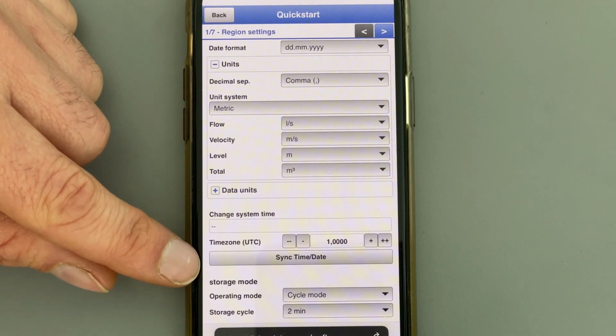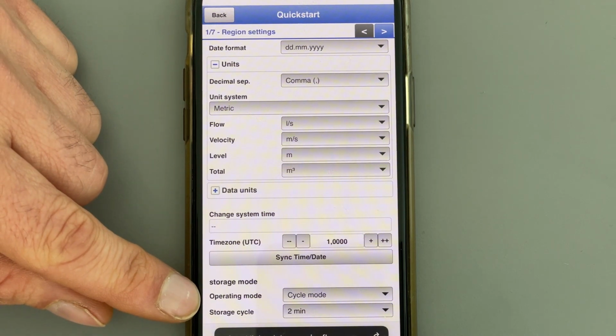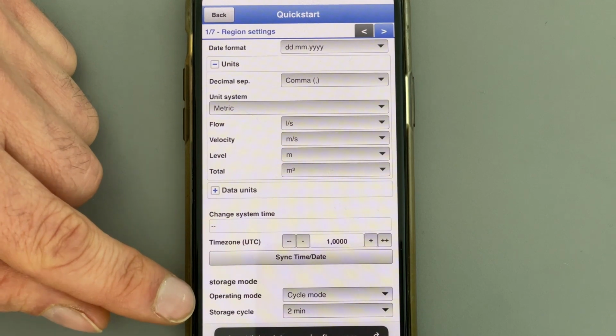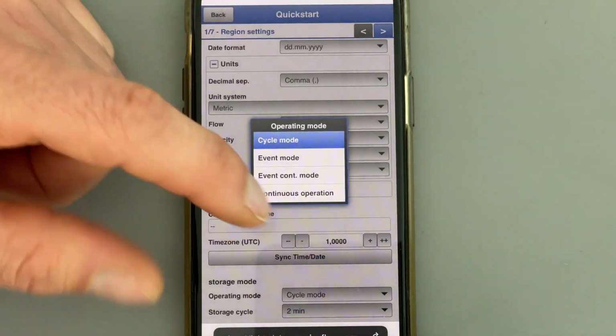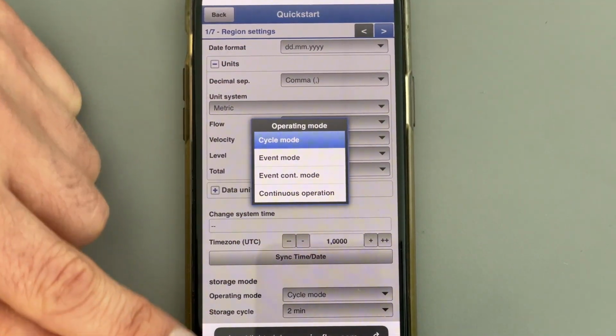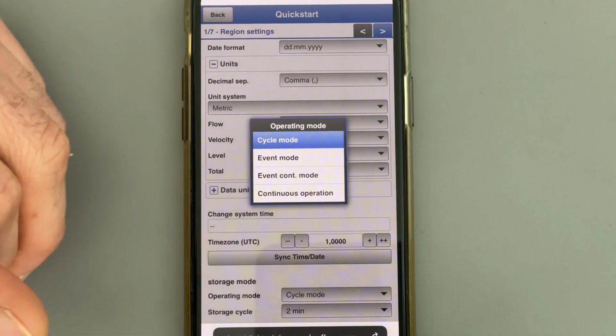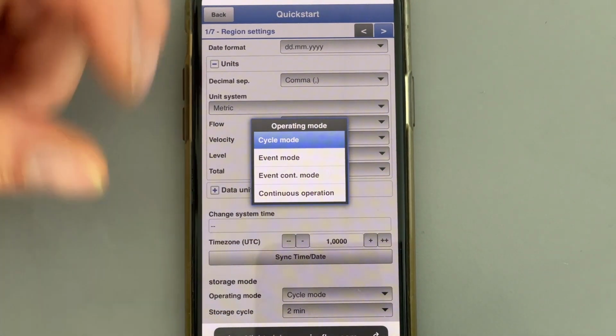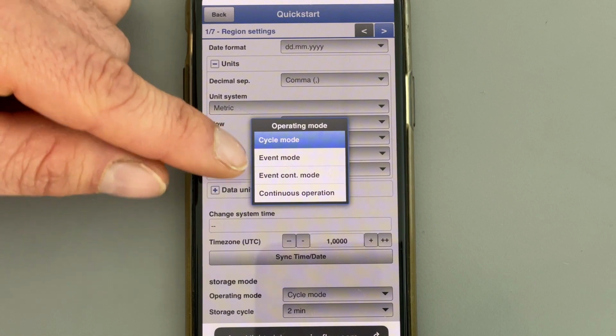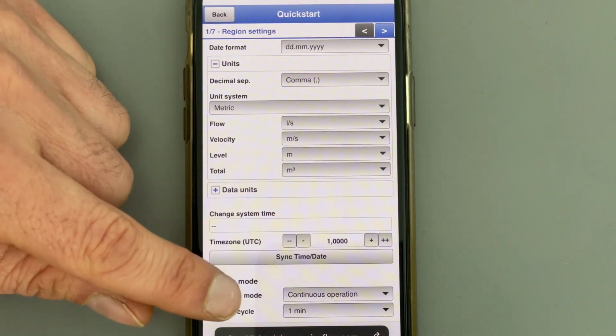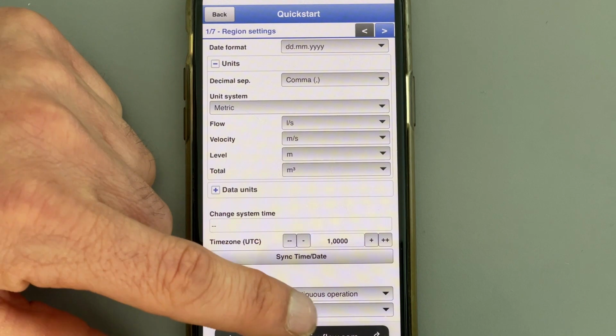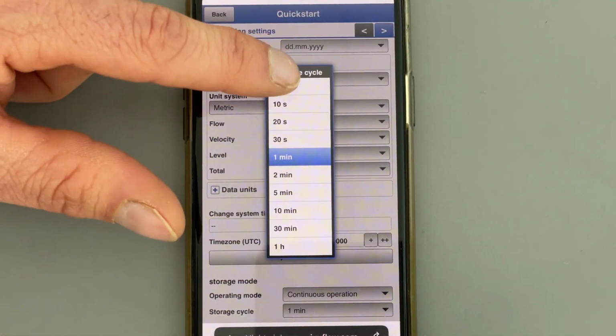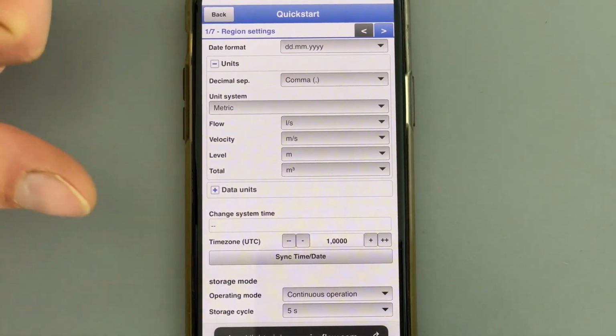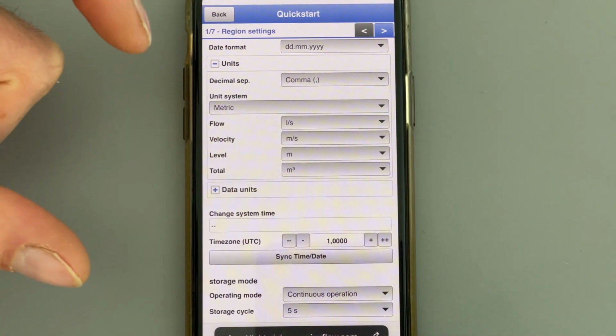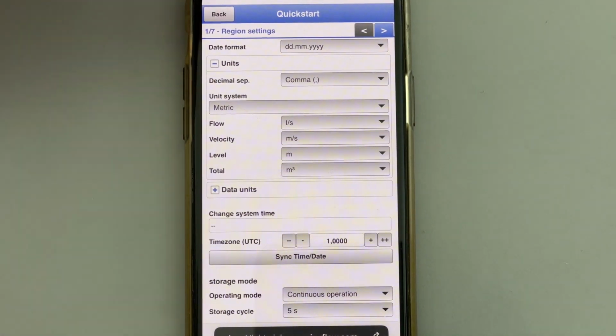System time, the time zone you're using, and here important is the storage mode. In the cyclic mode, the device will always go back to sleep between the measurement cycles. In this case, every 2 minutes it will wake up, take a recording, save it, and go back to sleep. In the continuous operation, the device never sleeps, and you can go down to 5 seconds. That's the highest resolution. That means every 5 seconds you have one data point.